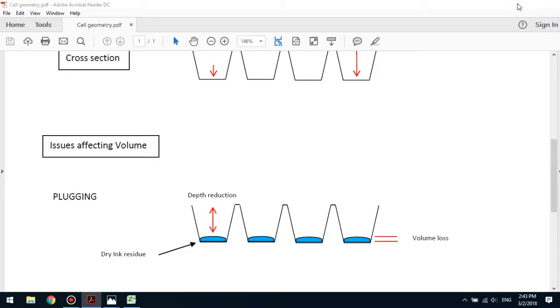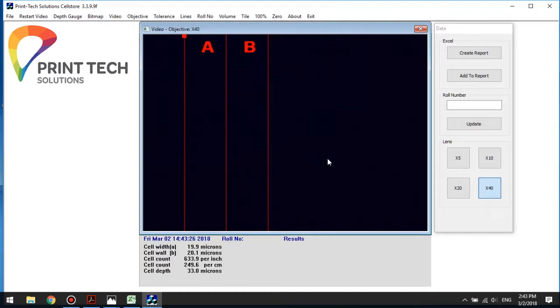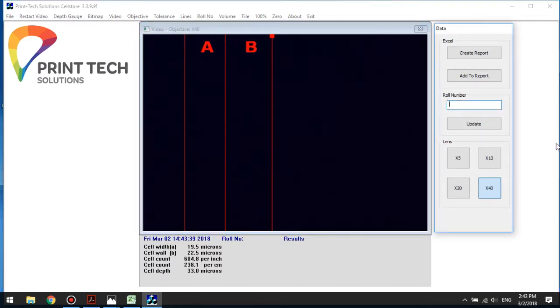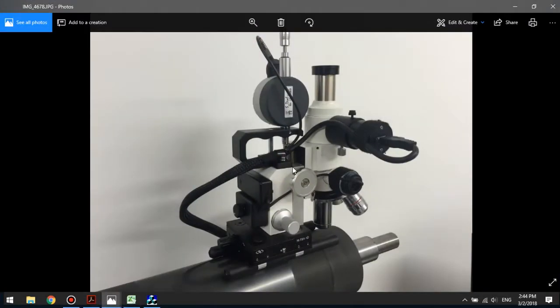Now let's take a look at the CellStore software. Here we are able to select our lenses and we have the vertical cursor for our measurement. The first thing I'm going to do is enter the roll number of the cylinder that I'm looking at. I'm going to put a generic in here and update that information, and now that has gone into the specifications box. Using the microscope, I'm going to obtain my image. This is the coarse focus and this is the fine focus. The coarse focus will give me 30mm of travel; the fine focus will give me 2mm of travel. I'm going to switch on the light source here — there's the control for the dimmer — and obtain my image.